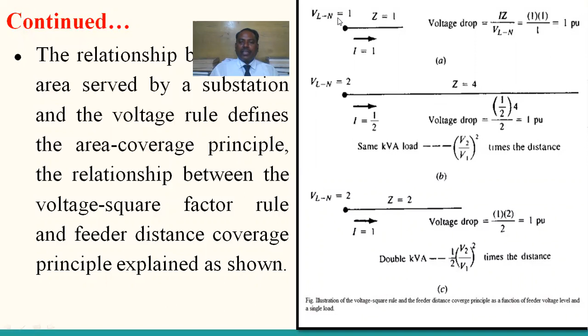So therefore, voltage drop is equal to I into Z. Z is 4, current is half, divided by the voltage which is 2, which is 1 per unit. So for the same kVA load, it covers (V2 by V1) square times the distance. So you see here the percentage voltage drop is also the same. Keeping the voltage drop constant and doubling the existing voltage results in covering 4 times the distance. As the voltage increases, the magnitude of the current is to be half.